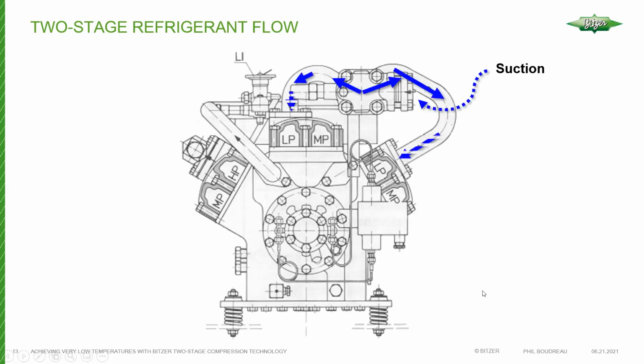So suction gas comes in, splits off via that suction manifold into the 2 low stage heads and cylinders. And then these cylinders compress the low pressure refrigerant from the evaporator up to the interstage pressure. And then after it leaves the valve plates of the low stage cylinders, the refrigerant enters this mixing pipe that you see here on the left. And then that travels back towards the motor.